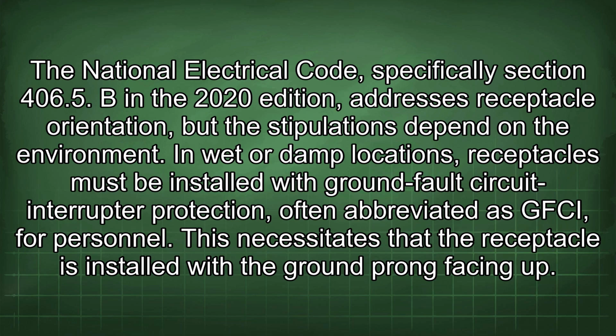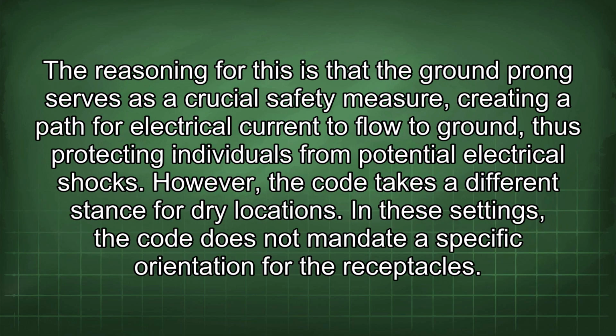In wet or damp locations, receptacles must be installed with ground fault circuit interrupter protection, often abbreviated GFCI, for personnel. This necessitates that the receptacle is installed with the ground prong facing up. The reasoning is that the ground prong serves as a crucial safety measure, creating a path for electrical current to flow to ground, thus protecting individuals from potential electrical shocks.